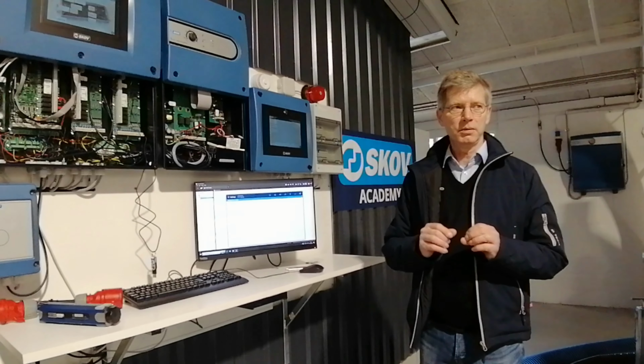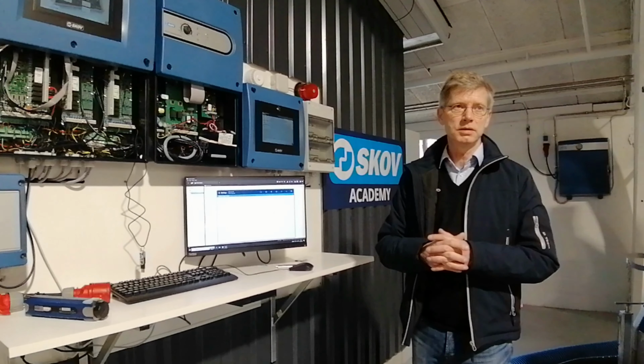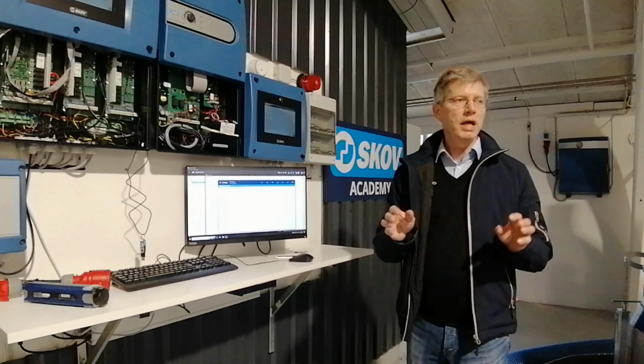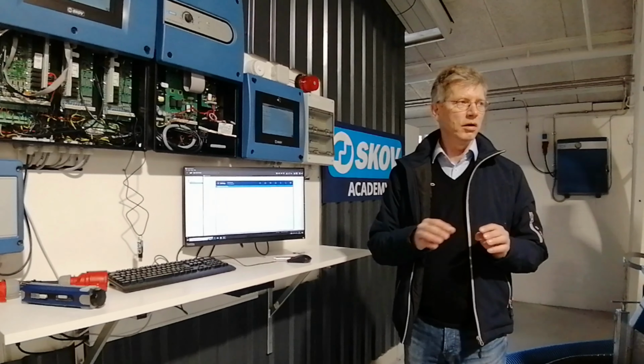The next thing I want to demonstrate, and you can try this yourself, is side curve adjustment. But you don't actually want to do side curve adjustment normally. I want to show you this, and you could use the smoke machine yourself, to illustrate what I've drawn on the whiteboard a number of times: air going along the ceiling, sticking to the ceiling because of the Coanda effect, then mixing and coming around.